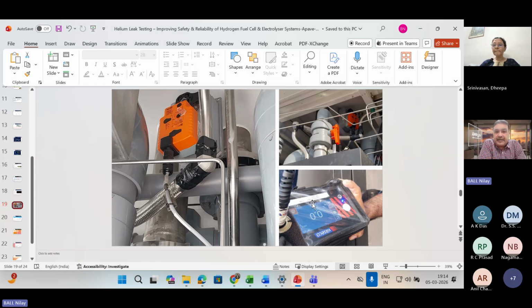You can use a hydrogen leak detection system, or helium leak detection system, through SCADA when the whole equipment is running. One automotive manufacturer found that when hydrogen flow is happening, if there's a leakage, the flow of hydrogen will change, in terms of 0.000001. So the SCADA system will detect the change of flow within that pipeline. These are very thin, sensitive pipelines. When they detect that change in hydrogen flow due to a leakage, the flow will reduce, and because of that reduction, the whole system will set off an alarm.